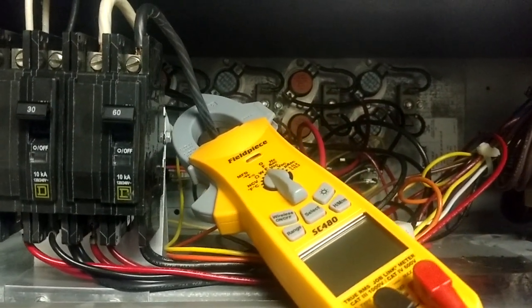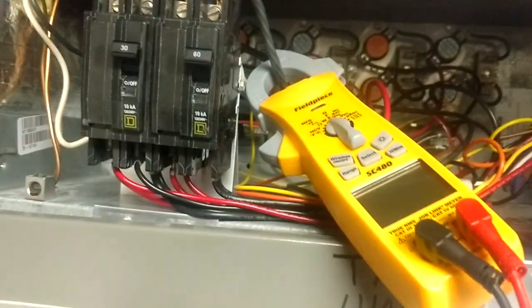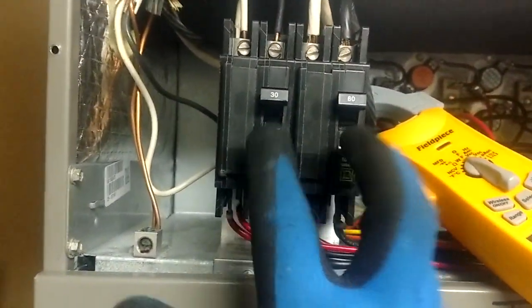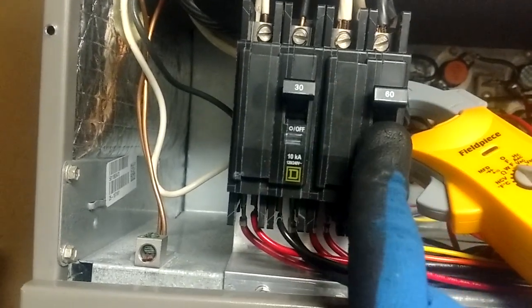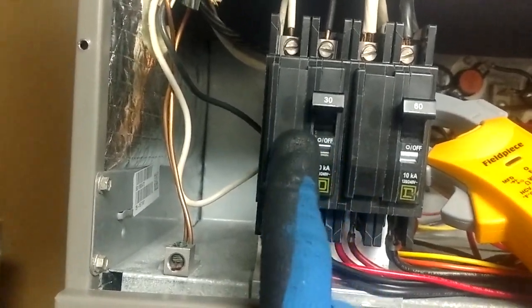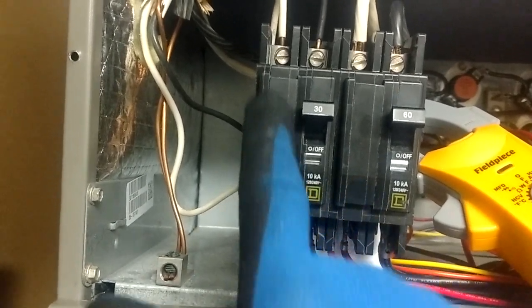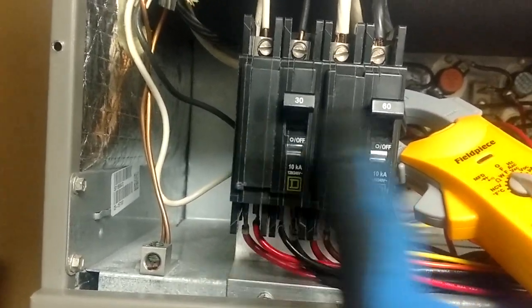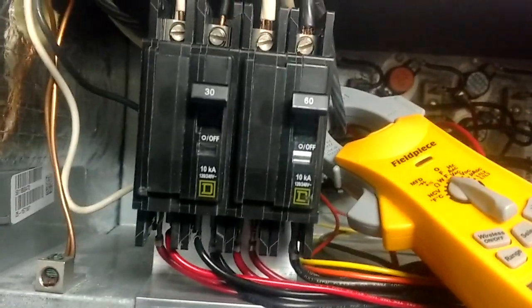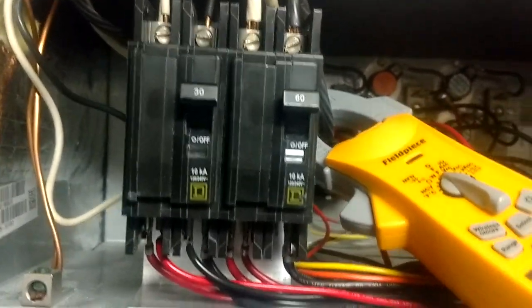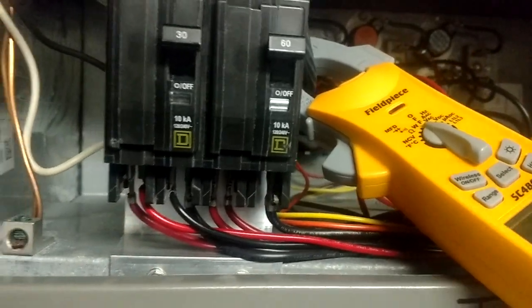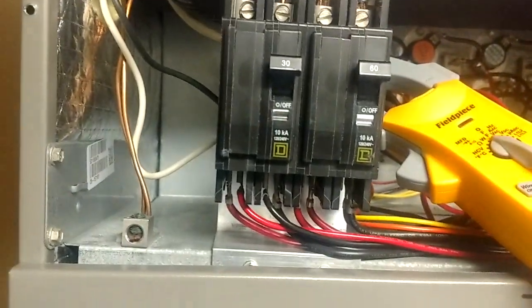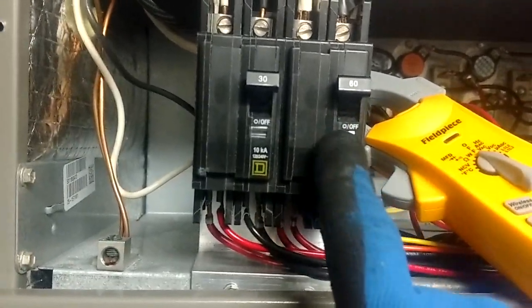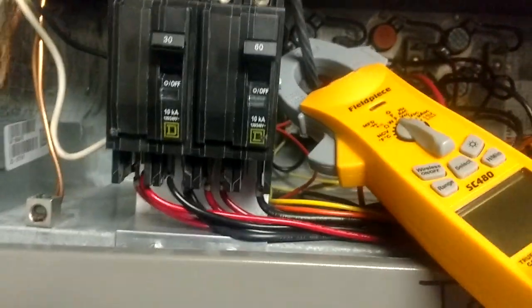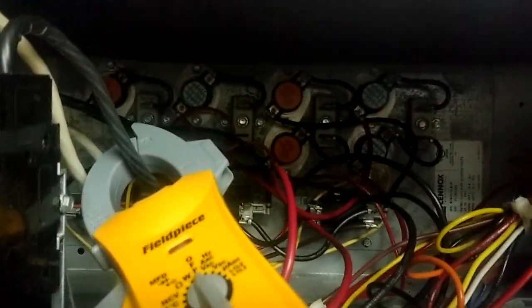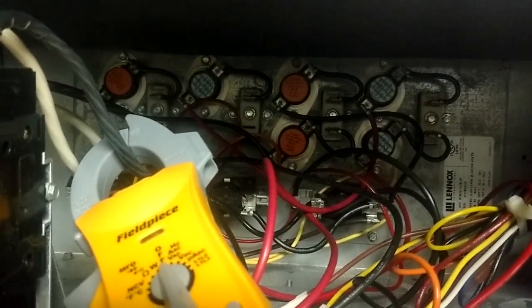Because we have this unit in emergency heat and we have the heaters fired up right now. And if you see right here, we have two breakers, a 30 and a 60. So we have 5 kW, or 5 kilowatts of heat over here, one heater, and we have two here, so that is 10 kW. So when we put this meter on watts and check that, we should come up somewhere close to 5 kilowatts over here and 10 kilowatts over here. So just visually it makes more sense because of all these heaters back here in the back.